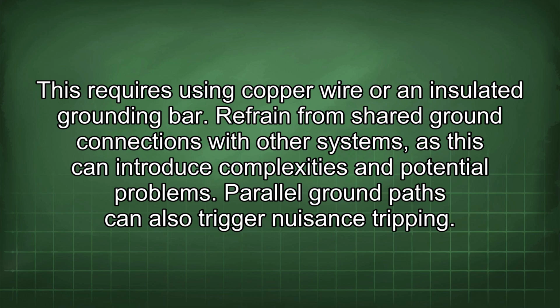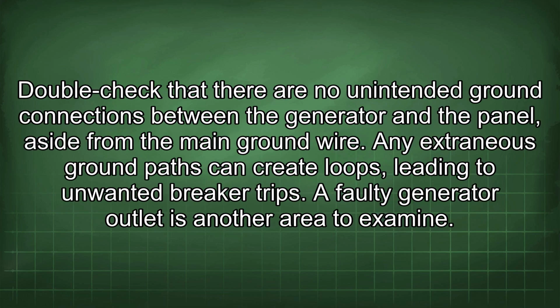Parallel ground paths can also trigger nuisance tripping. Double-check that there are no unintended ground connections between the generator and the panel, aside from the main ground wire. Any extraneous ground paths can create loops, leading to unwanted breaker trips.